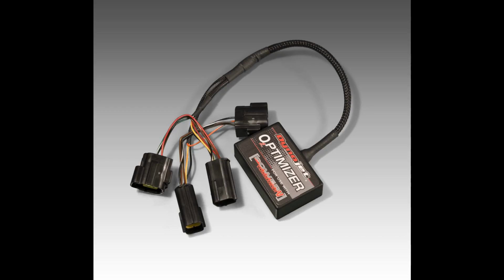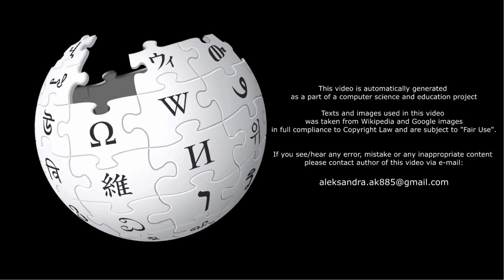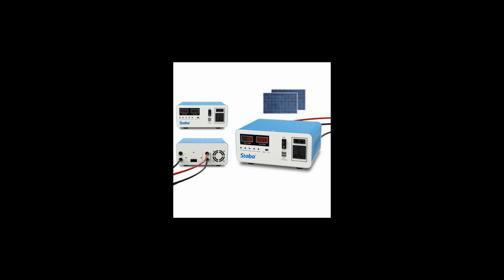However, this approach has the disadvantage of distributing the power conversion circuitry, which, in theory, is the expensive part of the system. Microinverters, at least as late as early 2011, had significantly higher price per watt. This leads, naturally, to the power optimizer concept, where only the MPPT system is distributed to the panels. In this case, the conversion from DC to AC takes place in a single inverter, one that lacks the MPPT hardware or has it disabled.